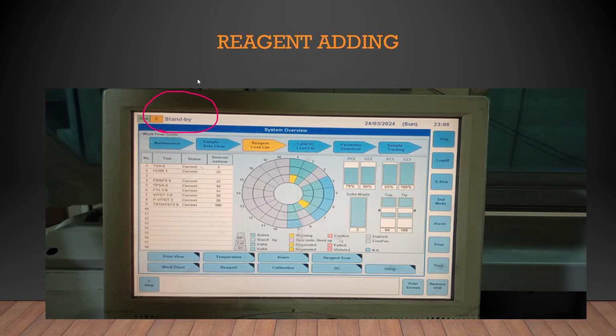Okay. So make sure that the instrument is in standby. Now this is very important. Many technicians keep making these mistakes. See, the instrument is not making any sound or no movement is happening, that doesn't mean you can do whatever you want with this instrument, because when the reagent probe will move, when the mixer probe will move, those cannot be predicted. Okay, so when you are adding the reagents and all, you have to make sure that the instrument is in standby position only.